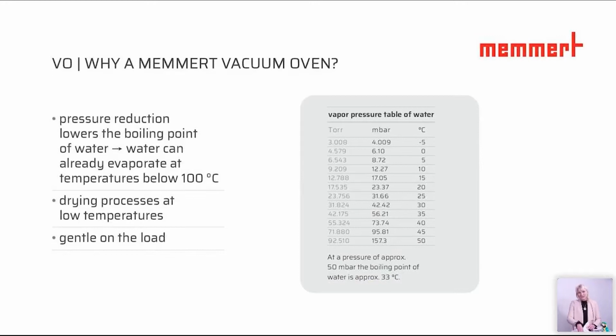When we talk about vacuum ovens, what does it actually mean, and for which purposes can this be used? A vacuum oven means we have a chamber, and this chamber is airtight. That means we go down in pressure, we take out the air, and whenever you reduce the pressure, it also means the boiling temperature will be reduced.